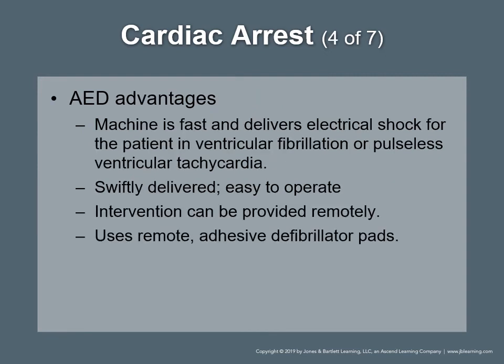AED advantages. The machine is fast and delivers an electrical shock for the patient in ventricular fibrillation or pulseless V-tach. It can be delivered within 1 minute of your arrival at the patient's side. They are easy to operate. Paramedics do not have to be on the scene to provide this critical intervention, and a shock can be given through remote adhesive defibrillation pads.